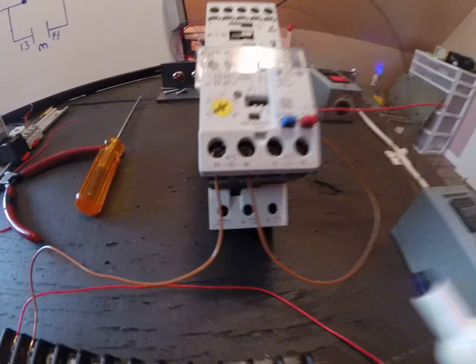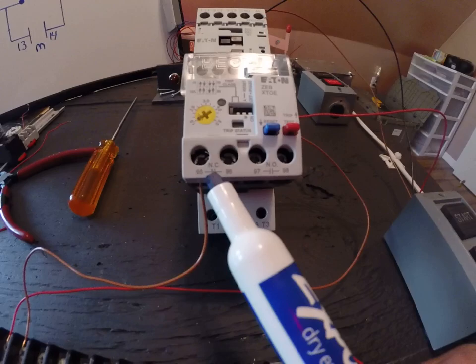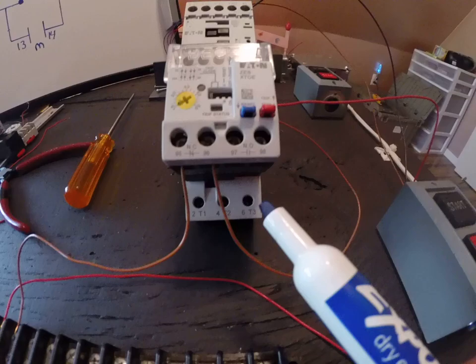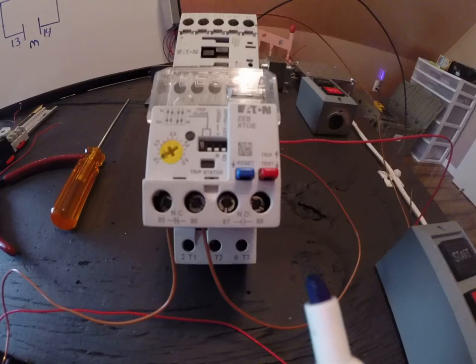Well in this particular setup, what you're going to see is there's an auxiliary set of contacts down here - one set is normally closed and it has numbers on it, 95 and 96. And then you got another set of contacts that are normally open, 97 and 98.